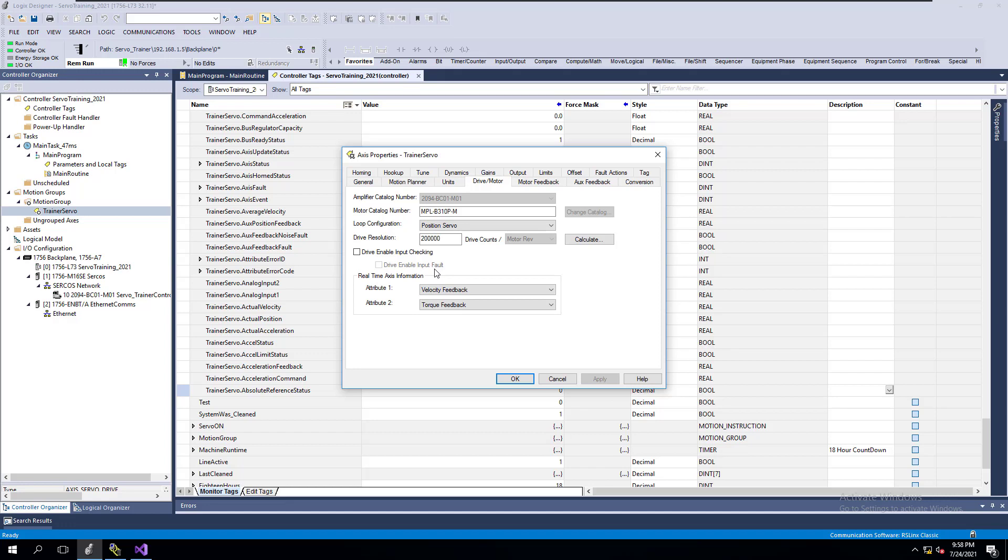It is working and again, do not change that. That is there by design of your OEM or by design by your manufacturer or whoever you're actually troubleshooting. So make sure you just verify that. Go ahead and look at the prints or trace the wiring down or look in the program to see if sometimes it's just as simple as hitting a reset button. Sometimes machines need to be reset and that is because of a safety protocol.